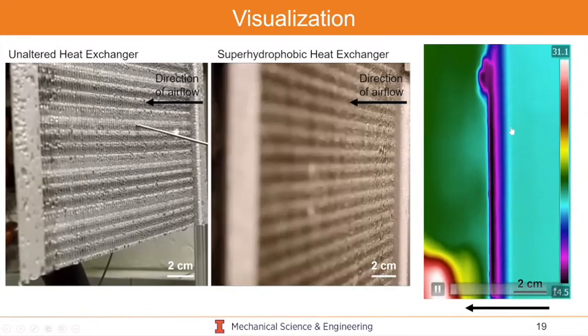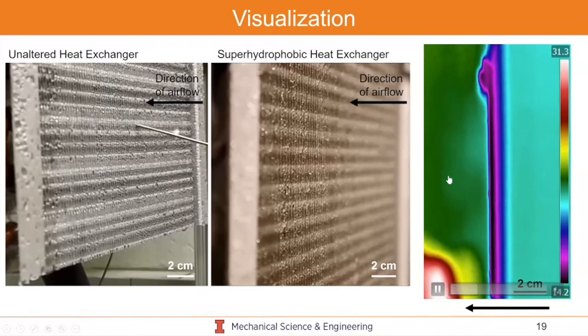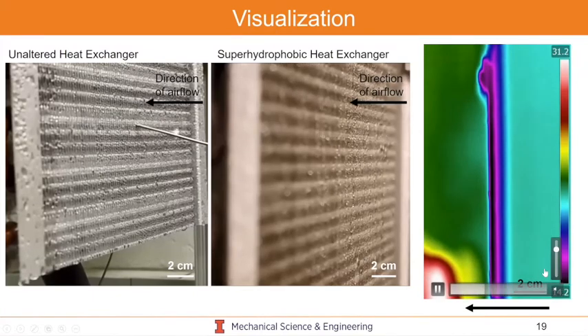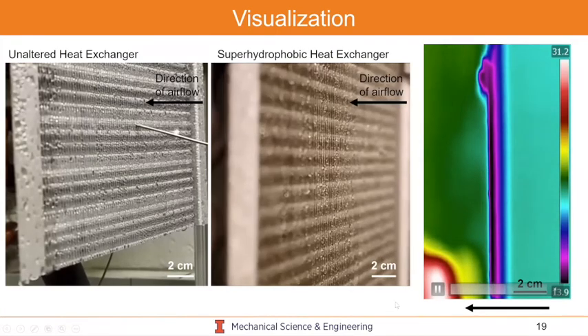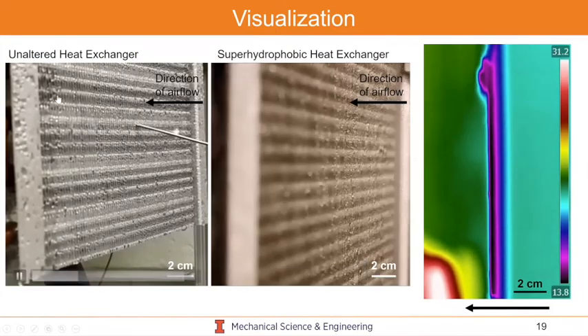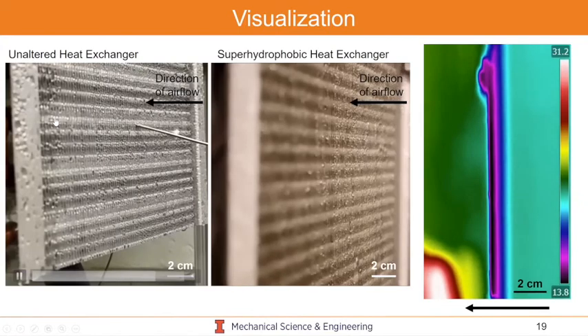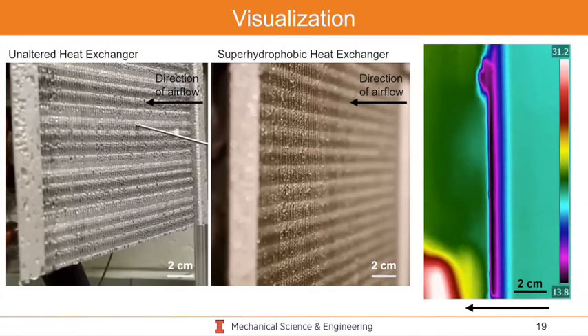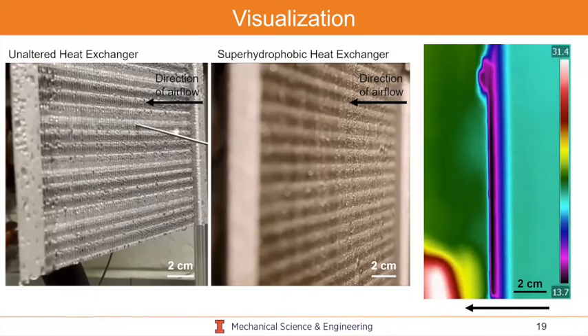This is more clearly seen on this infrared image, where even though your airflow is right to left, you're actually seeing droplets eject from the heat exchanger and leave into the airstream. The main reason this helps with frosting is because it's these droplets which accumulate on the super-cooled heat exchanger that eventually ice up and block all the air passages, making the process very inefficient and forcing you to run a defrost cycle.